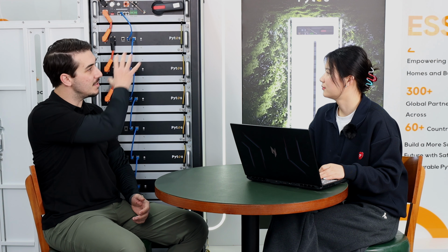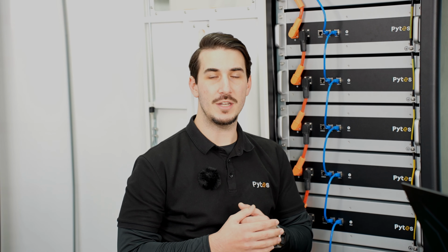So the difference is that for high voltage, we're connecting in series—going positive to negative to raise the voltage on the DC bus—whereas with low voltage systems, we're connecting our batteries in parallel: positives to positives, negatives to negatives. When we do parallel connections, we maintain the same voltage but increase our amp hour capacity, or our charge and discharge capacity.